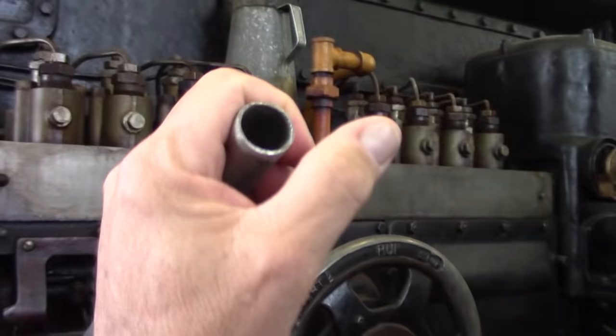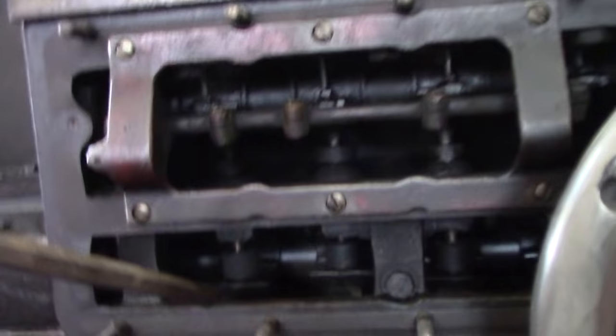Here's the Fairbanks Morse engine on this side. What's this bar? This bar is what he's got in here — he's priming it. He needs to reprime this engine; he couldn't get it started the other day, and he's just jacking the fuel pumps to work the air out of the injector lines and such.